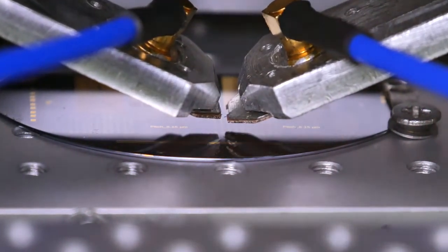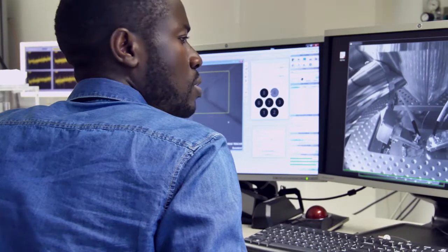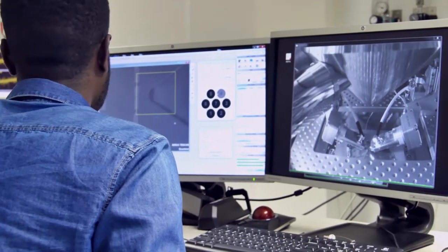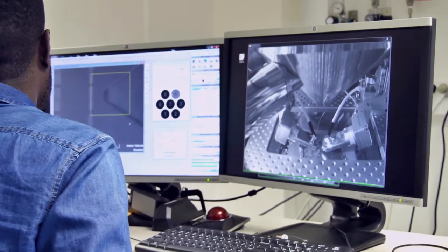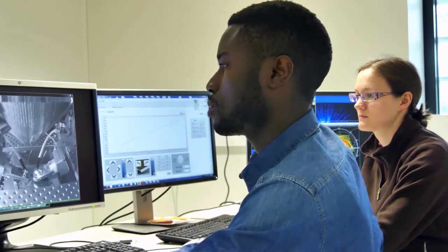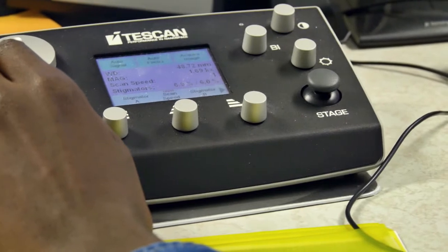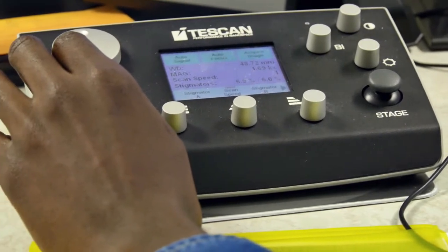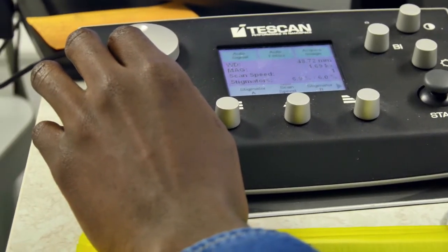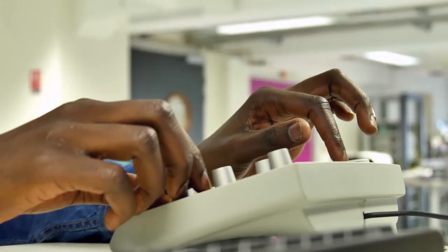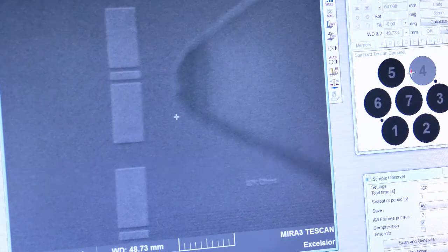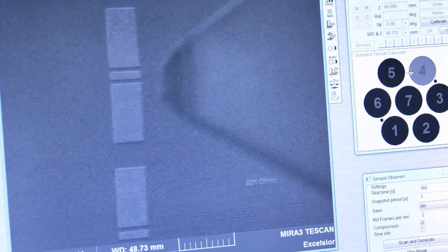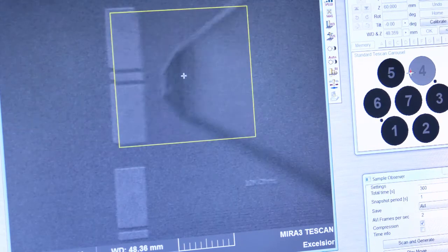The probe's motion is achieved through the use of 4 piezoelectric nanomanipulators, 2 for DC and 2 for HF, with displacement resolution higher than 10 nanometers. SEM navigation in a controlled high-vacuum environment with sub-10 nanometer resolution under low electrical field, with beam blanking options to limit the invasive action of the electron beam on the DUT, allows the precise positioning of the probes on a sample.